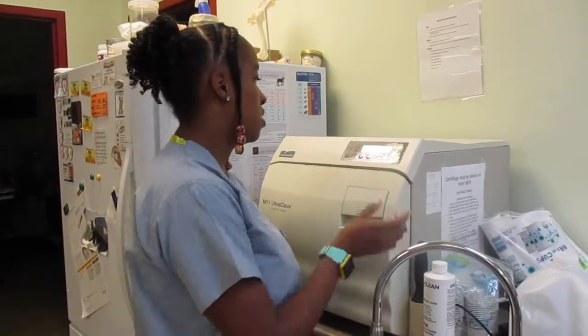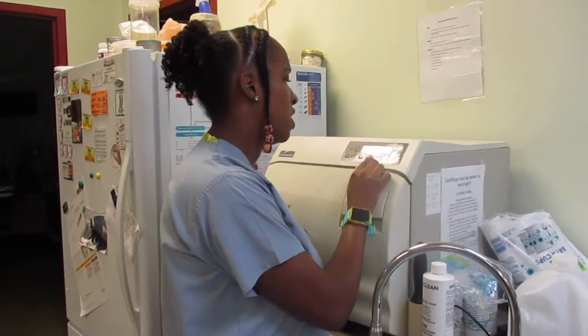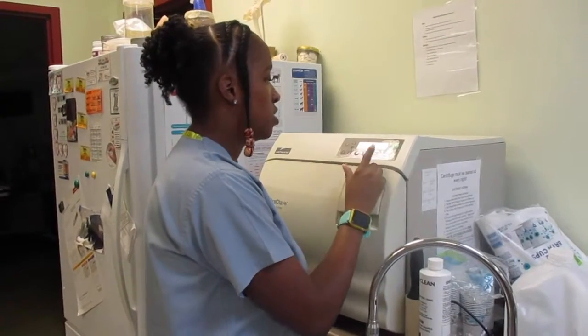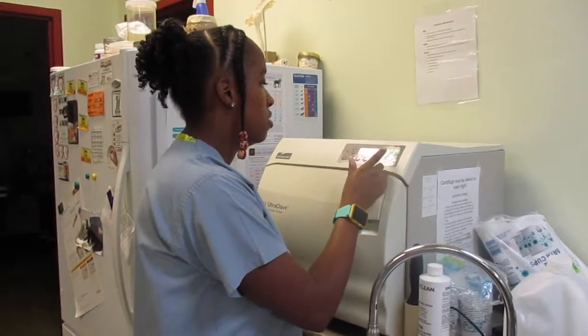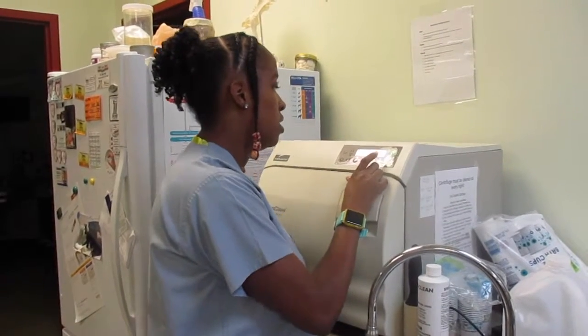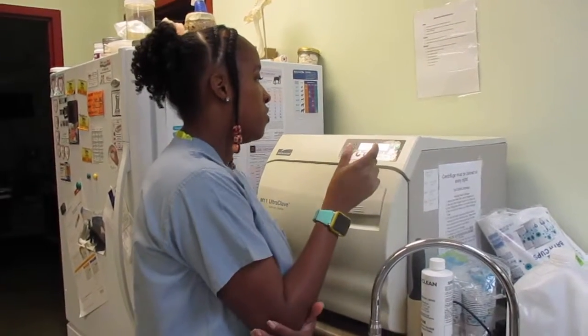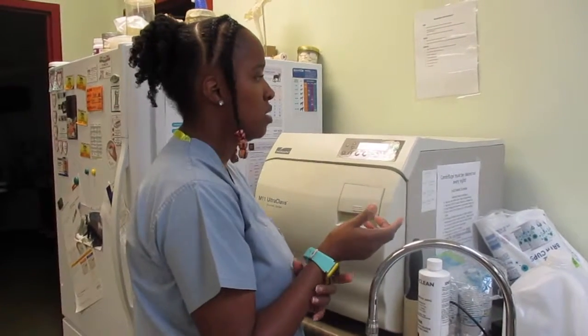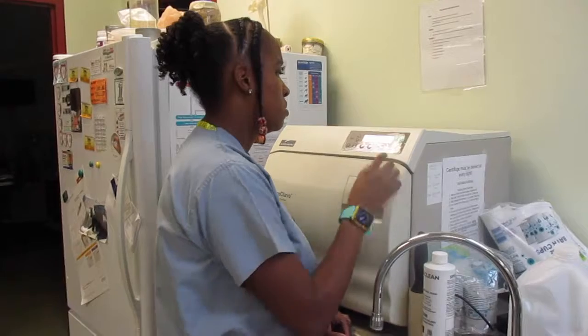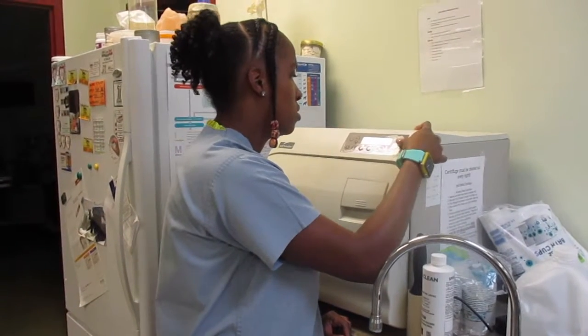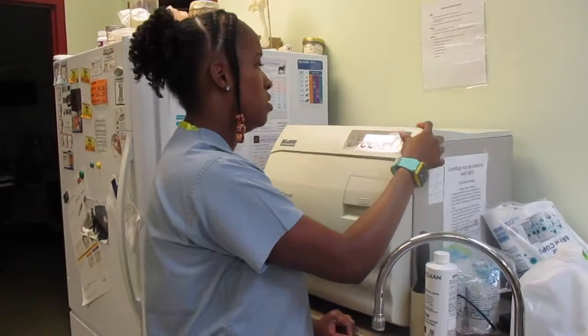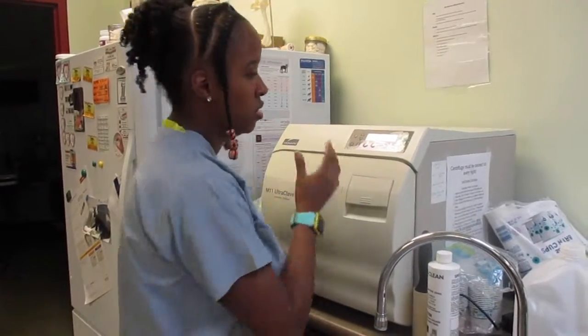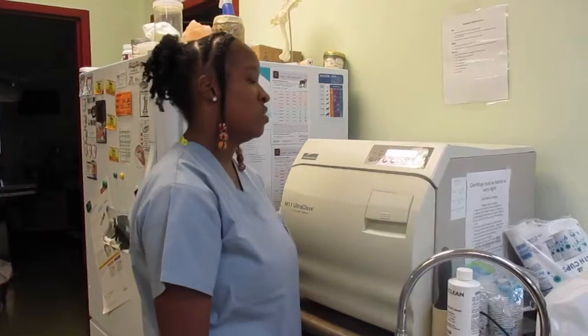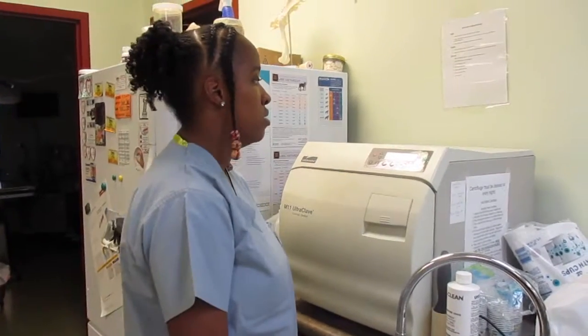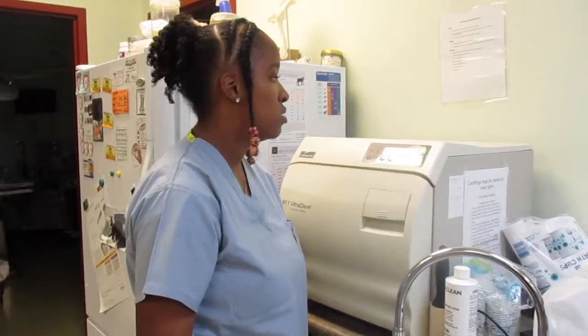Alright, so once the packs are in there, you're going to go ahead and go to this. There's a few cycles. So there's unwrapped, pouches, packs, and hand pieces. So I'm going to go ahead and use packs. And then it tells me it takes about 30 minutes. And the temperature is typically between 250 to 270 degrees. So it's going to fill the chamber. The distilled water will fill the chamber. It takes about 10 minutes for that, and then the heating process will begin.